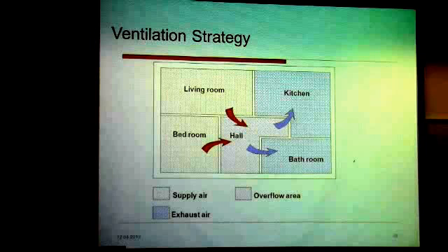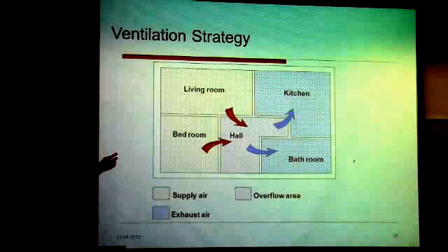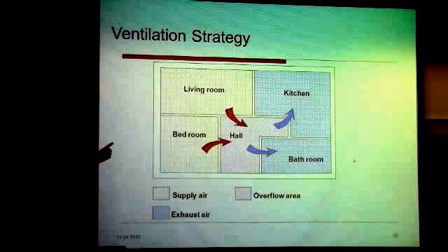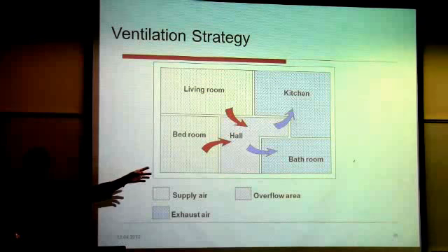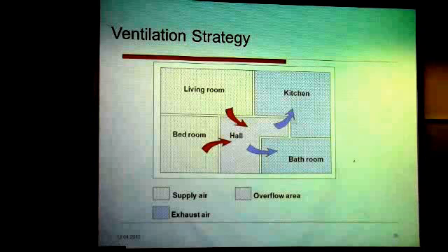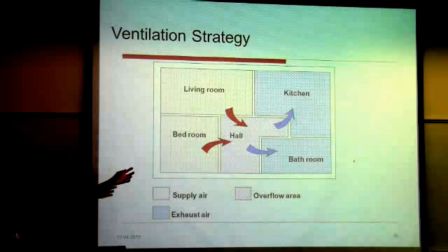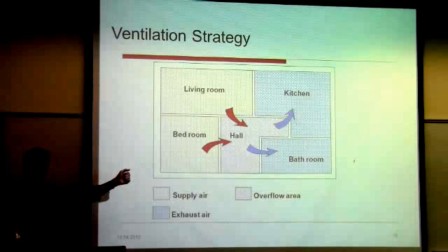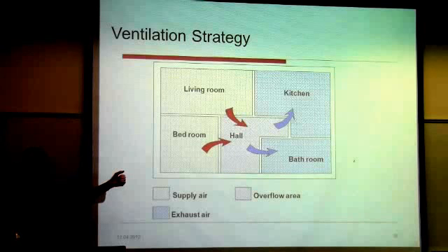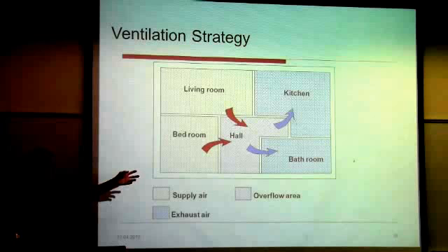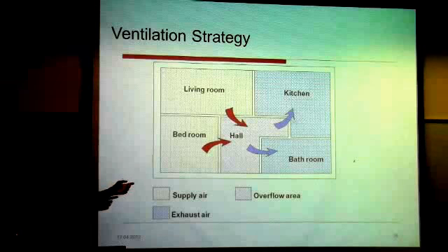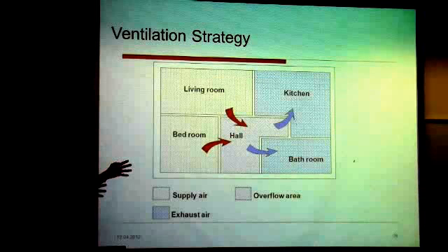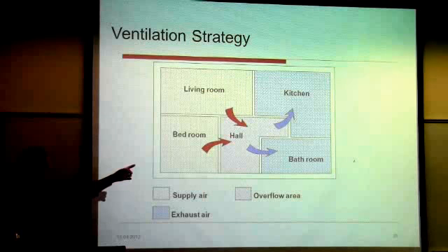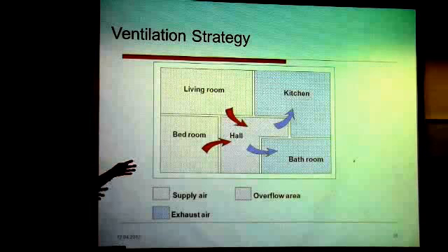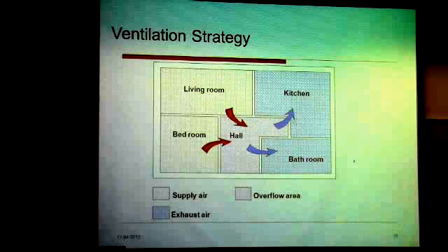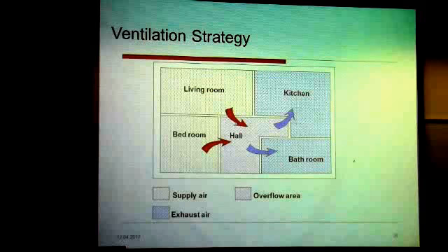In our ventilation strategy, we're adding the fresh air to the bedrooms and living room spaces, and then we're exhausting from the kitchen and bathrooms. We'll talk about it later also, but for the code requirements for bathroom exhaust, you can do a continuous bathroom ventilation instead of just the intermittent bath fan. So this is working 24 hours a day, supplying constant fresh air. And like I said, you're supplying there and taking out of the wet areas where fumes and exhaust fumes might happen.